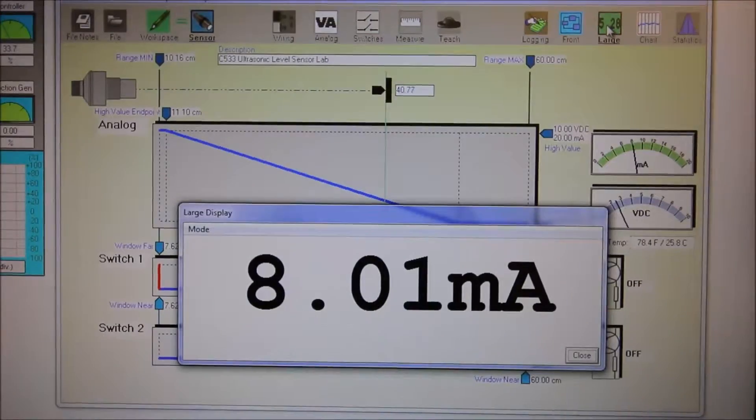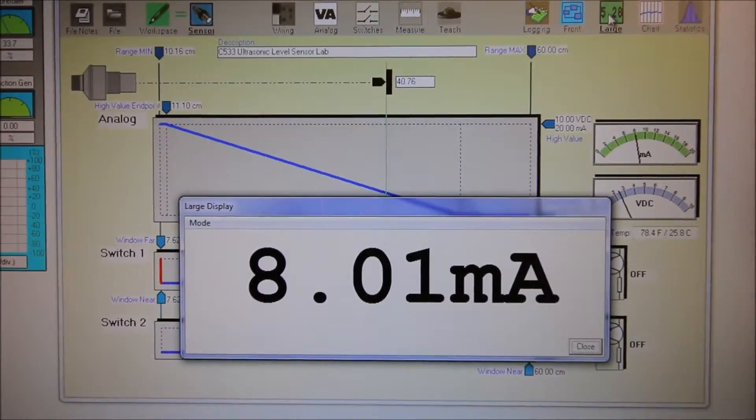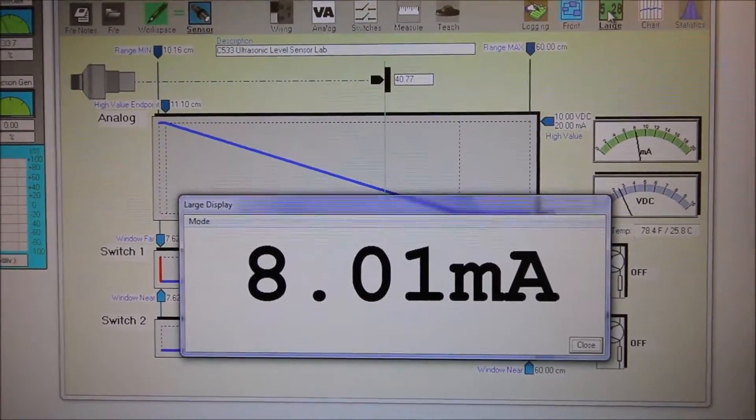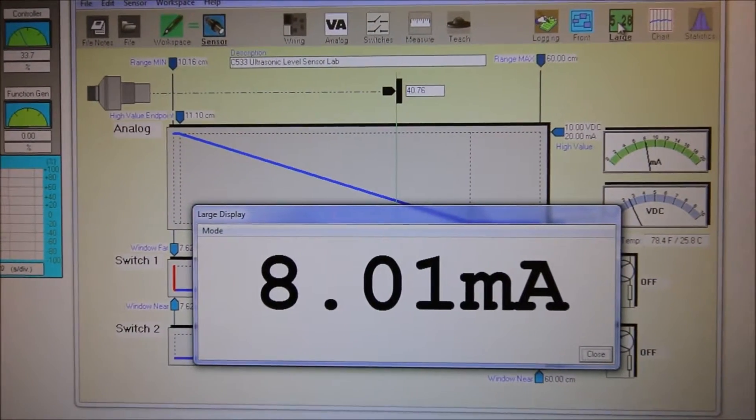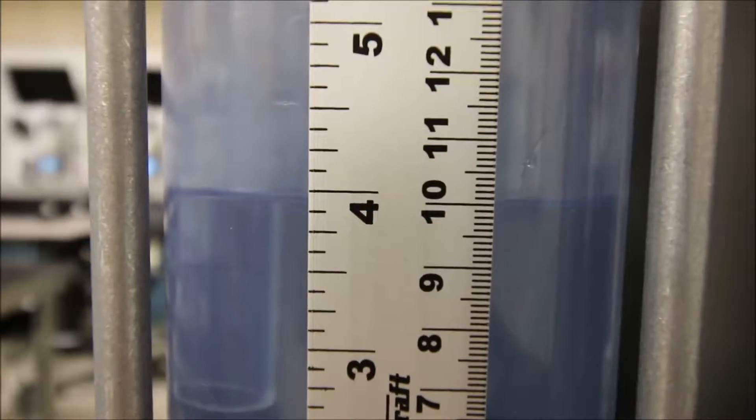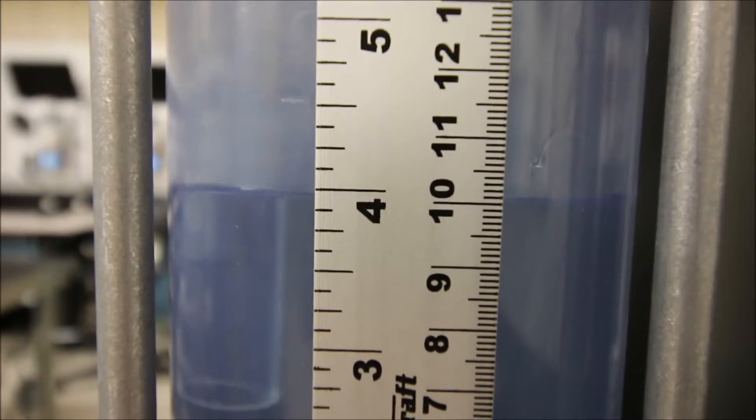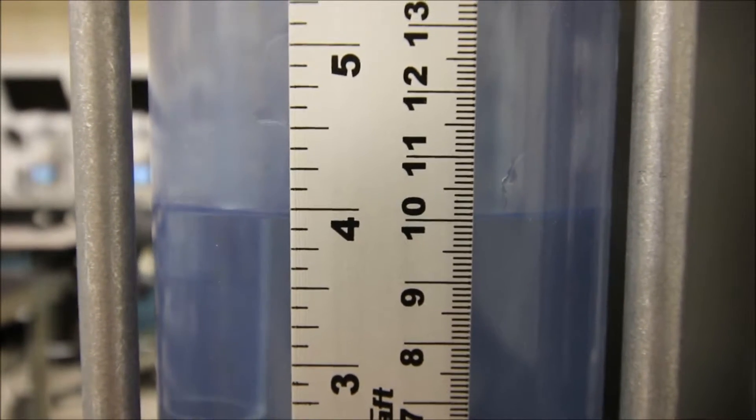Okay, let's drop it down 10 more centimeters. That'll bring us to 10 centimeters, that's our lowest value, and the lowest value on a 4 to 20 milliamp signal would obviously be 4 milliamps.